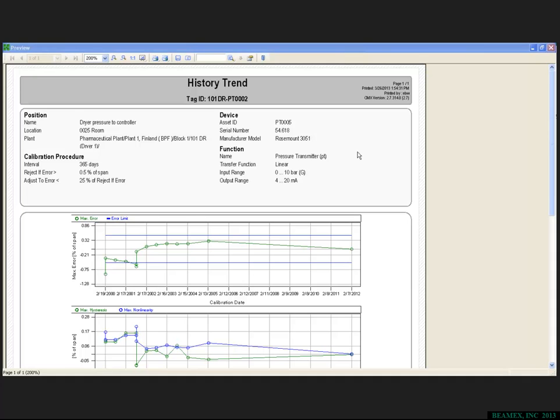Typically, if it's a minor out of tolerance, it would be adjusted and brought back into tolerance through the adjustment process. If it's a major, a lot of times they can be adjusted, sometimes they can't. If it was significant, then that would be a flag to determine, okay, do I need to replace the instrument? Do I need to decrease the calibration cycle? And you would have to look at the data to make that determination. Typically a major out-of-tolerance condition would require you to reevaluate, depending on the calibration cycle, 30 to 50% of the cycle. A significant out-of-tolerance event would typically require you to reduce the calibration cycle by half and follow up at that point to see if it was able to maintain its tolerance.